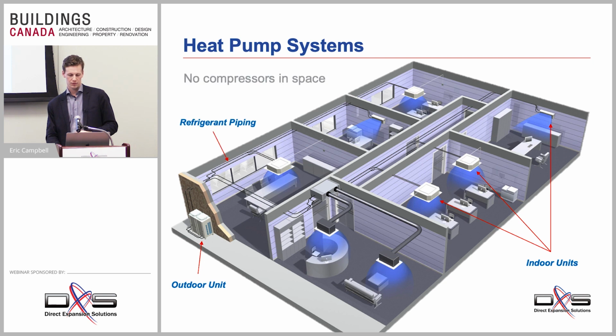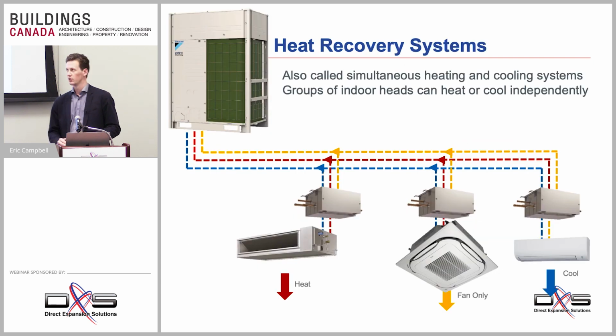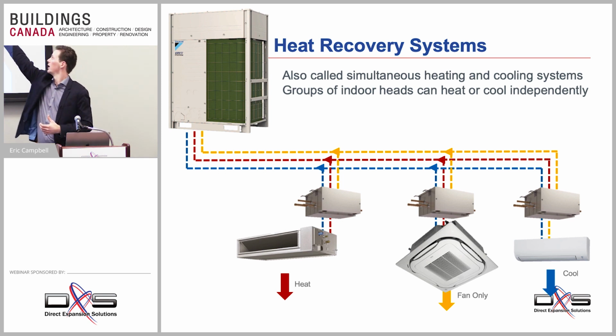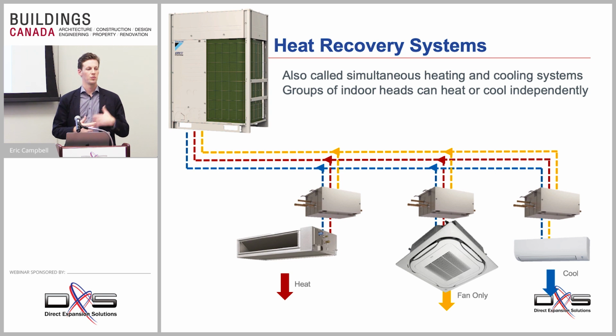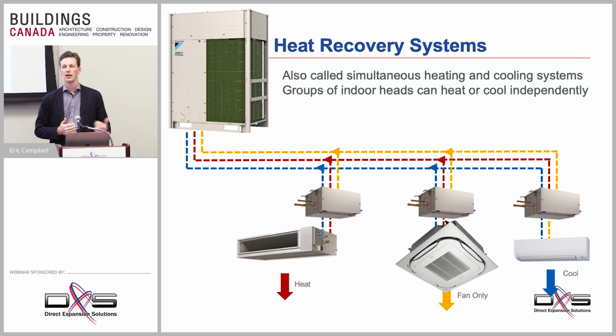Just going to skip to the next slide. So the second type of system we have is what we call a heat recovery system, or a simultaneous heating and cooling system. Now what we've done, we've added an extra component, what we call a branch selector box in the middle there. And that allows us, along with a third pipe, which is a dedicated hot gas line, to have that heating independence. So you can have some units in heating and some in cooling. There's no real limit on how many units need to be in cooling and how many need to be in heating for the system to function.